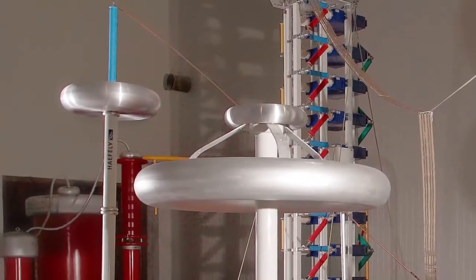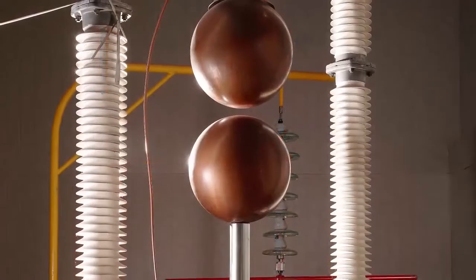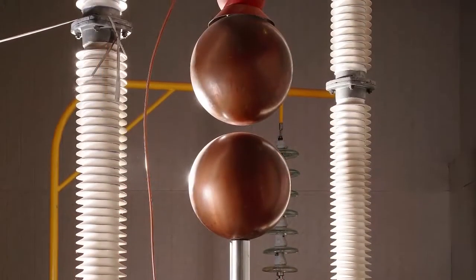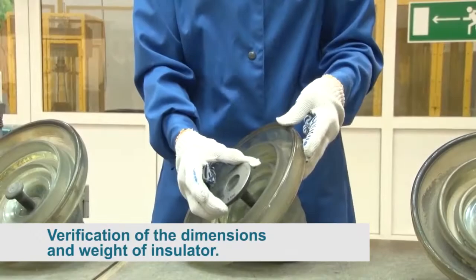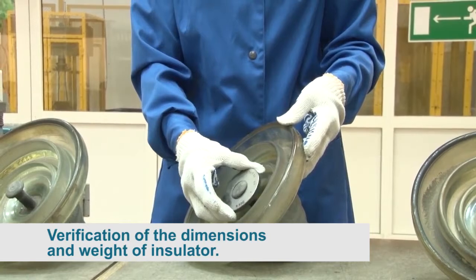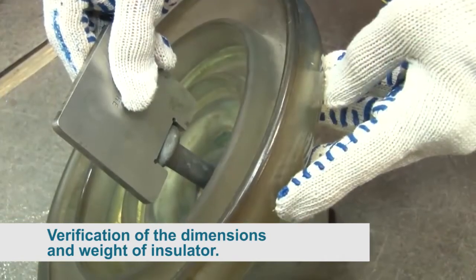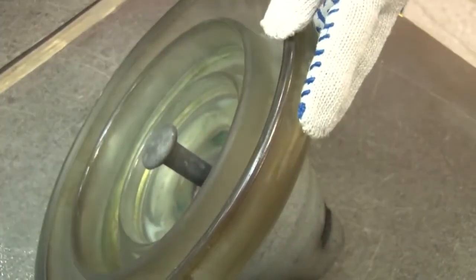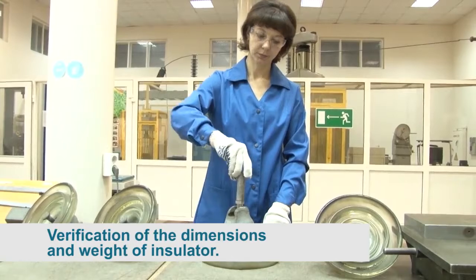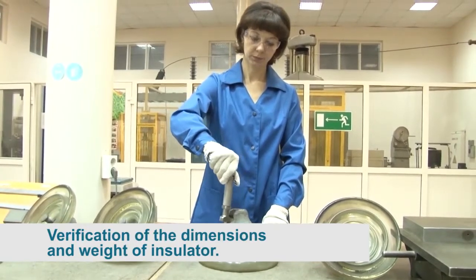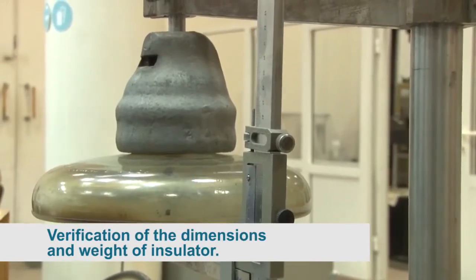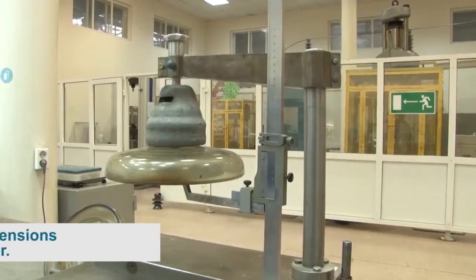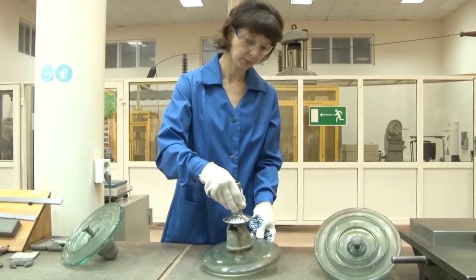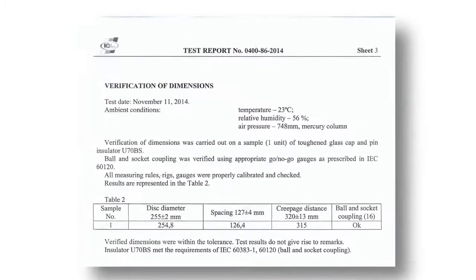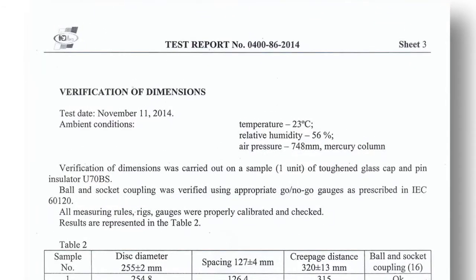25 insulators were chosen for tests. 12 different tests were performed for each type of insulator. Verification of the dimensions and weight of insulator type PS12A. The creepage distance range is within 317 to 322 millimeters. Verification of the dimensions and weight of insulator type PS70E. Creepage distance is 315 millimeters, which is within acceptable standards. Insulators meet the IEC requirements.